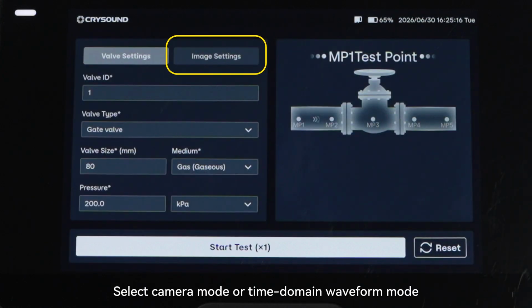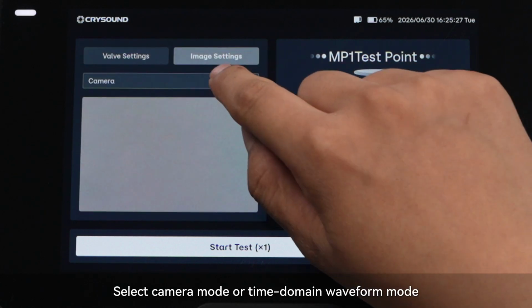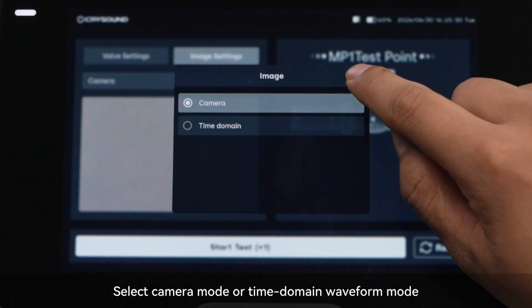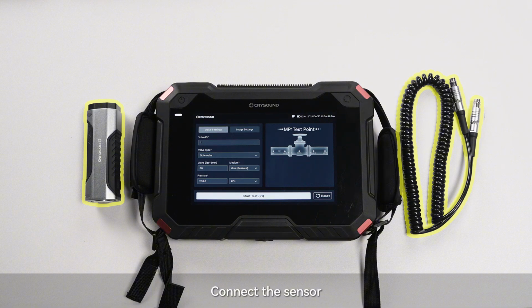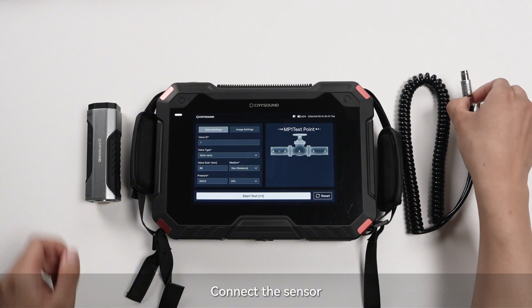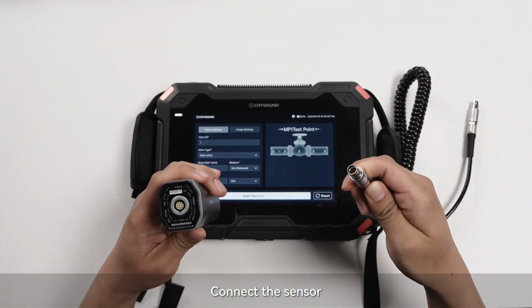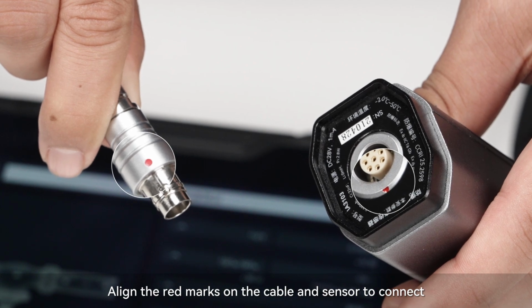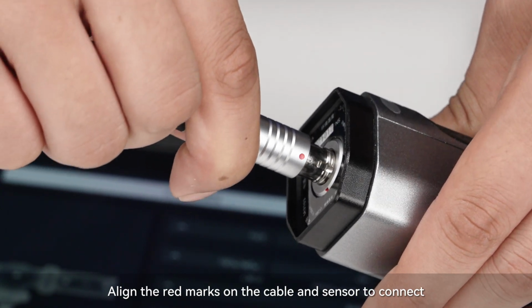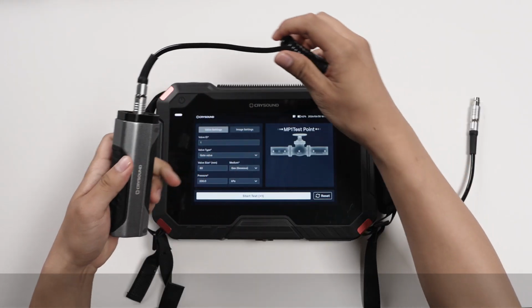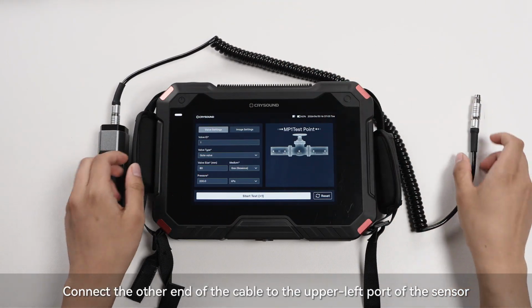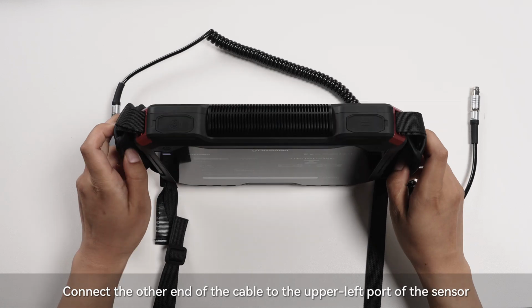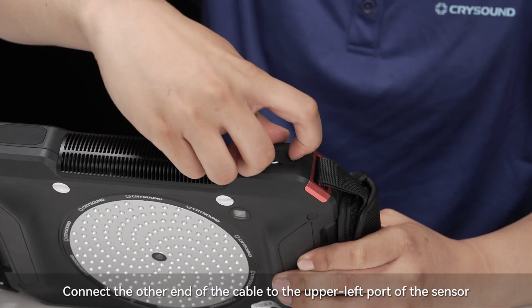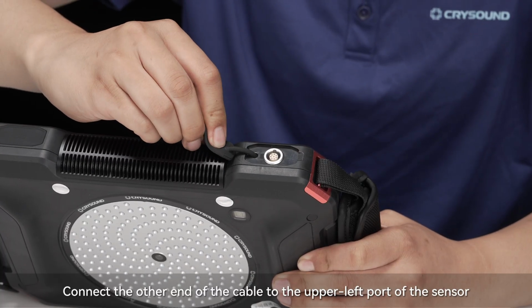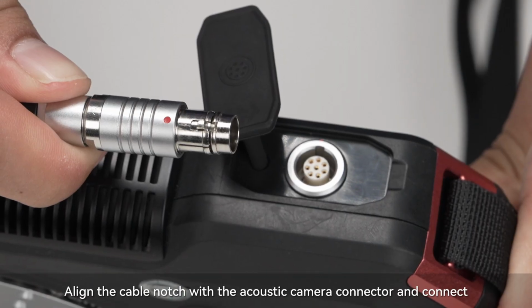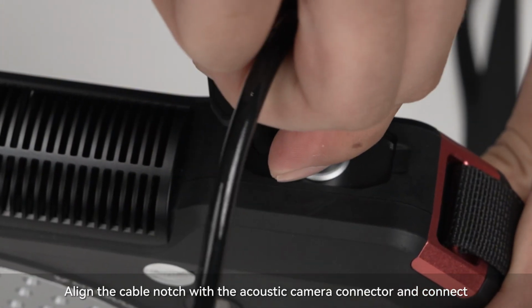Select camera mode or time domain waveform mode. Connect the sensor. Align the red marks on the cable and sensor to connect. Connect the other end of the cable to the upper left port of the sensor. Align the cable notch with the acoustic camera connector and connect.